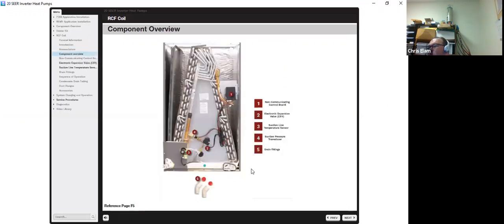So if you were to open one of these coils up, this is what you see here. This is that little box that I showed you. So right here, you've got your non-communicating board. You've got your EEV right here. The 4 is your pressure transducer. It's going to your line. Right here is your suction line temperature sensor. That's going to act as your sensing bulb. And then you also have your various drain fittings.